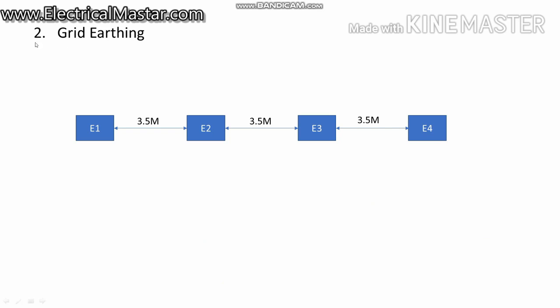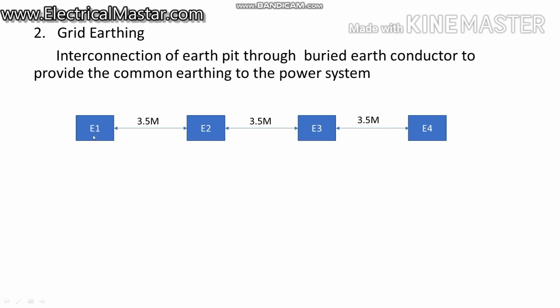The second significance is grid earthing. Grid earthing is simple. I told you about the individual earth pit connection. In the same way, you connect n number of earth pits together through earthing cable underground. This is called grid earthing. See here E1, E2, E3, E4. These are the earth pits. We connect each earth pit with a minimum distance of 3.5 meters through underground bare copper conductor cable. Likewise, if you connect n number of earth pits, it is called grid earthing.